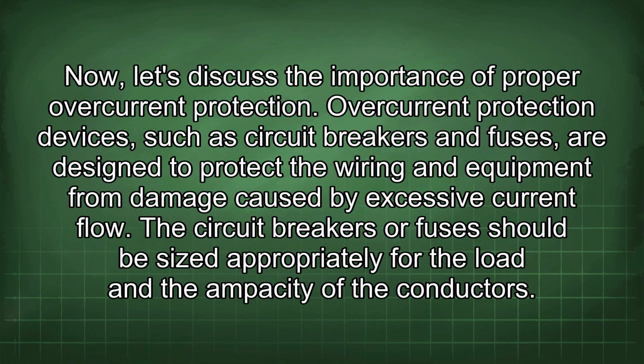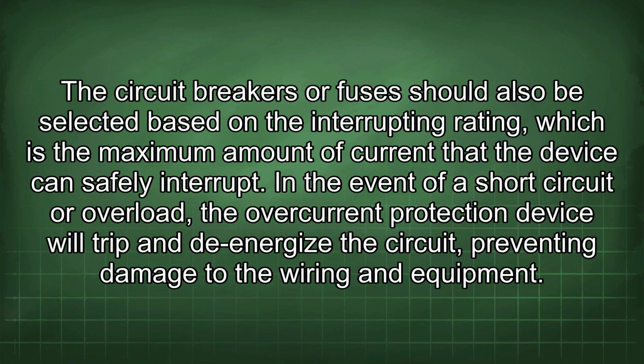Now, let's discuss the importance of proper overcurrent protection. Overcurrent protection devices, such as circuit breakers and fuses, are designed to protect the wiring and equipment from damage caused by excessive current flow. The circuit breakers or fuses should be sized appropriately for the load and the ampacity of the conductors. They should also be selected based on the interrupting rating, which is the maximum amount of current that the device can safely interrupt. In the event of a short circuit or overload, the overcurrent protection device will trip and de-energize the circuit, preventing damage to the wiring and equipment.